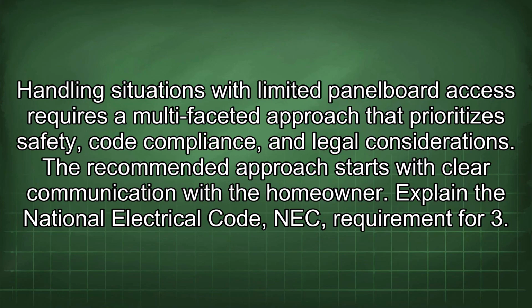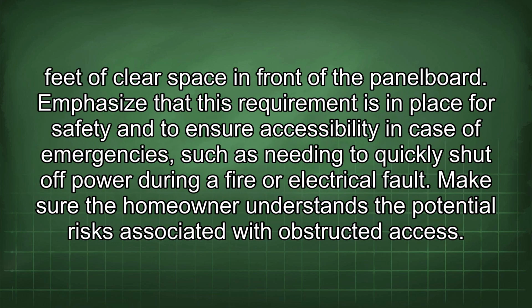Handling situations with limited panelboard access requires a multifaceted approach that prioritizes safety, code compliance, and legal considerations. The recommended approach starts with clear communication with the homeowner. Explain the National Electrical Code (NEC) requirement for 3 feet of clear space in front of the panelboard. Emphasize that this requirement is in place for safety and to ensure accessibility in case of emergencies, such as needing to quickly shut off power during a fire or electrical fault. Make sure the homeowner understands the potential risks associated with obstructed access.